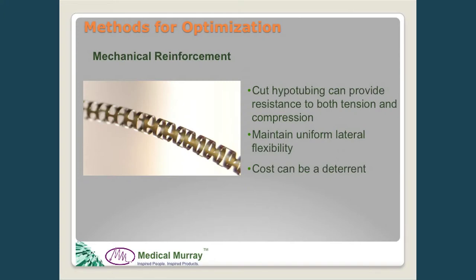One way to get around that is cut hypotubing. This method uses virtually an endless number of patterns that can be designed and cut out of tubing, allowing a shaft design that resists both compression and tension while maintaining uniform lateral flexibility. The downside with this design is cost, especially for a longer catheter that may require this component over its full length.